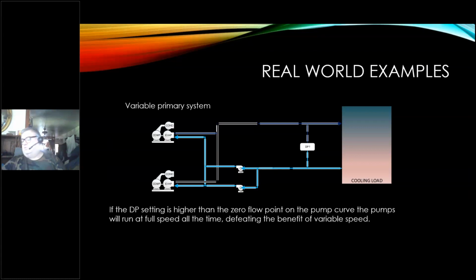So what we did, we started using a more reasonable approach to setting that pressure differential. Started getting some actual change in speeds on the flow. It improved the performance of the chillers to where now we take full advantage of both variable speed on the pump and the variable loading on the chillers. As the load changes, the chillers change their loading, and they operate at a better kW per ton point now that it's actually working right.